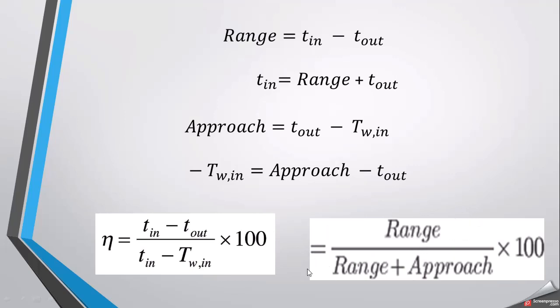This gives the efficiency of the cooling tower. We only need the inlet temperature, outlet temperature, and wet bulb temperature of the air entering the tower. Alternatively, if you know the range and approach, you can use η = range / (range + approach) × 100. The key concept is that it is not possible for a cooling tower to reduce water temperature below the wet bulb temperature of the surrounding atmosphere.